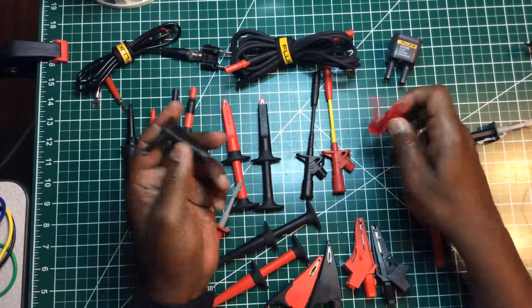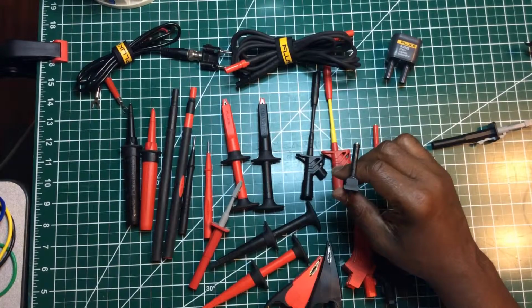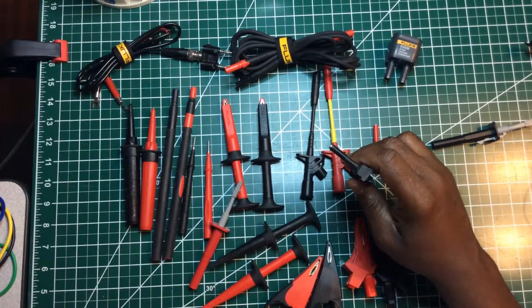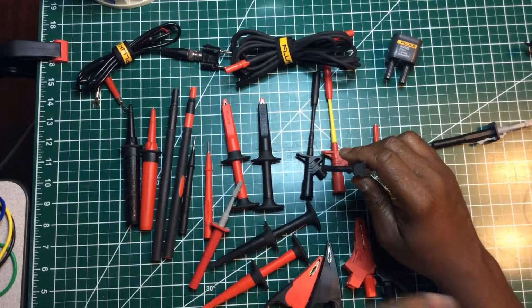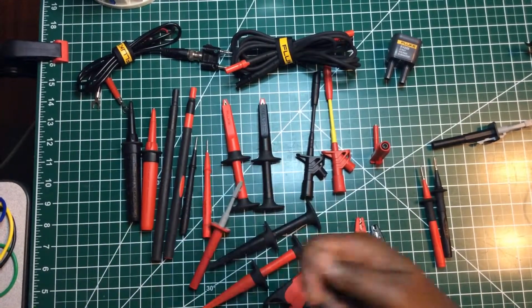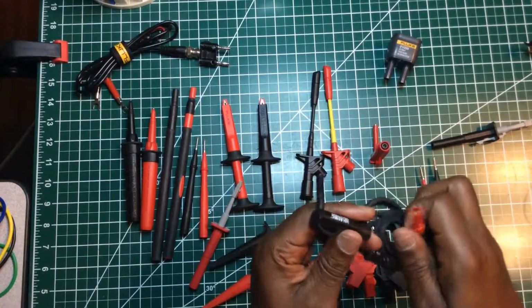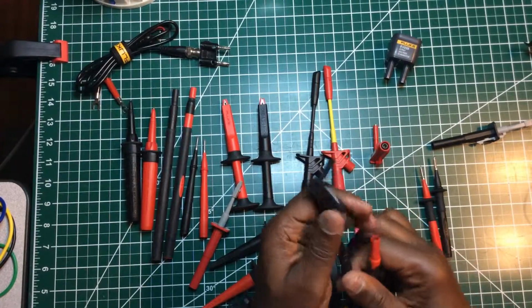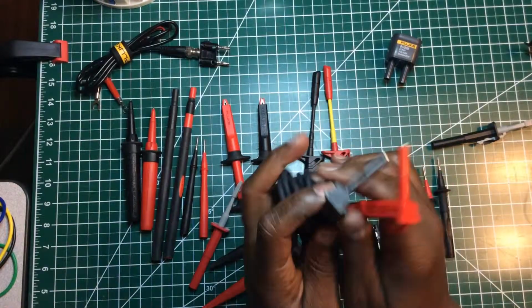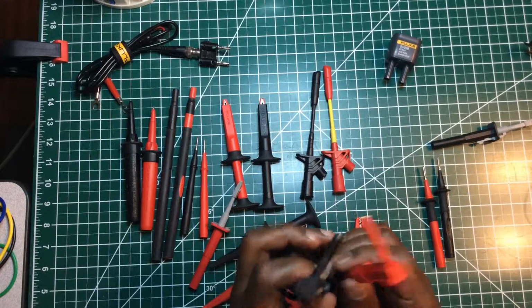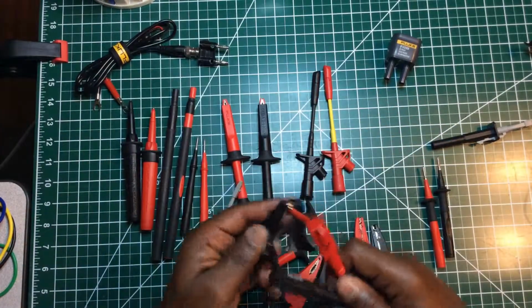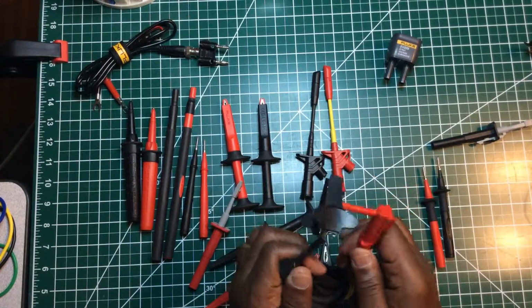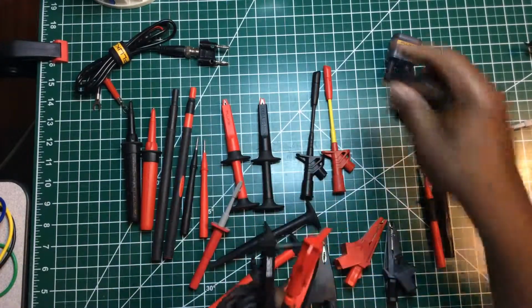Now these are made by AEMC, and these are magnetic probes. Sometimes you're working in a panel, not your normal 200 amp electrical panel, but an industrial setting with a terminal block where you can't put your alligator clips on, and you can't hold this all day trying to get a reading. So what you'd do is take this, put one on here, put the other one on here, then put the other side into your meter. It magnetically holds onto the screw. These are some pretty strong screws, I tell you. Let me show you so you can get an idea, pretty strong screws, and that's how that works.